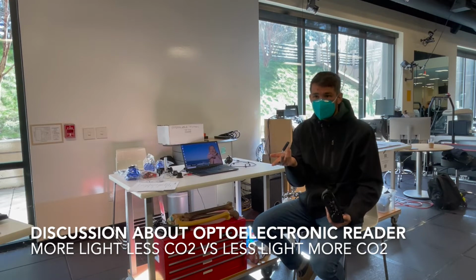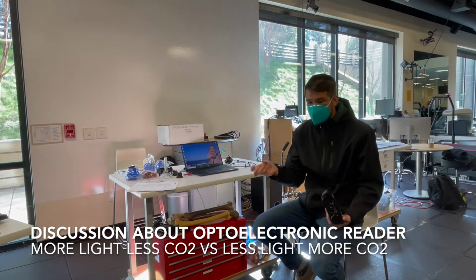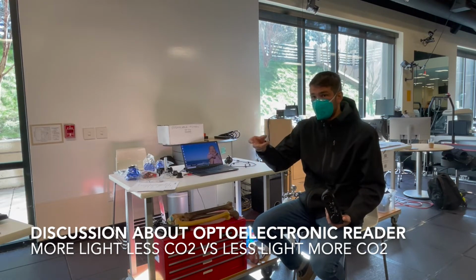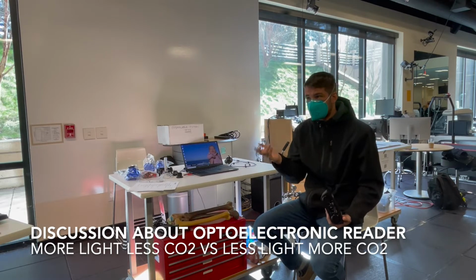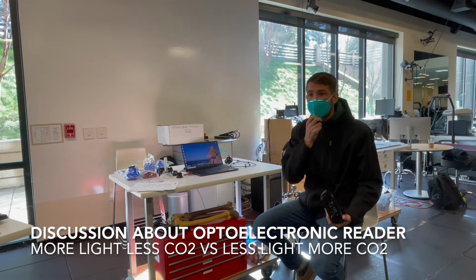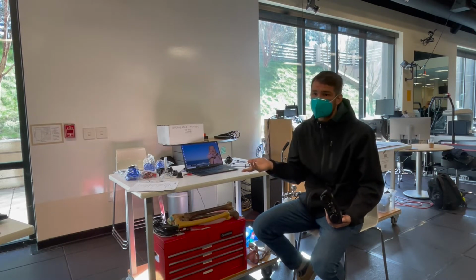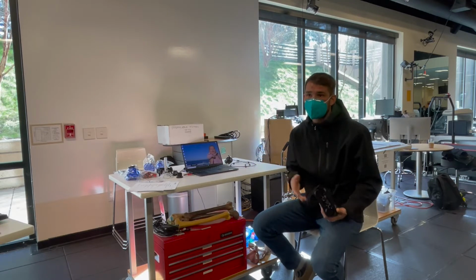And then the less light that is received, the more CO2; more light, less CO2. So you can see how that can throw off the calibration or the measurement if the calibration wasn't done accurately.